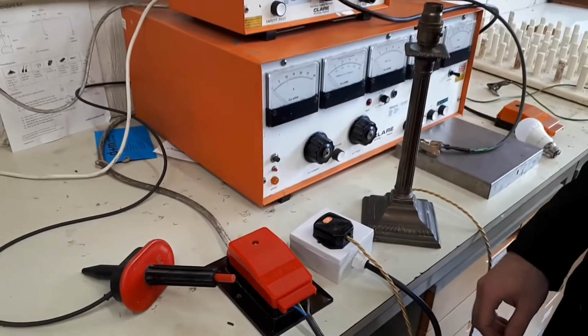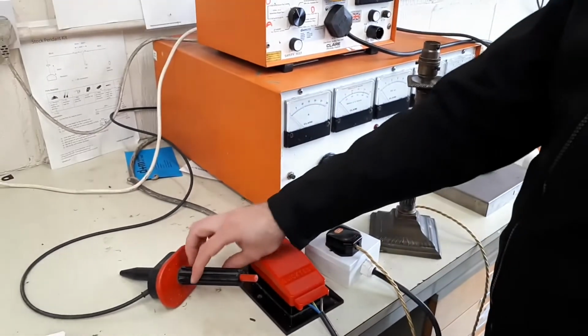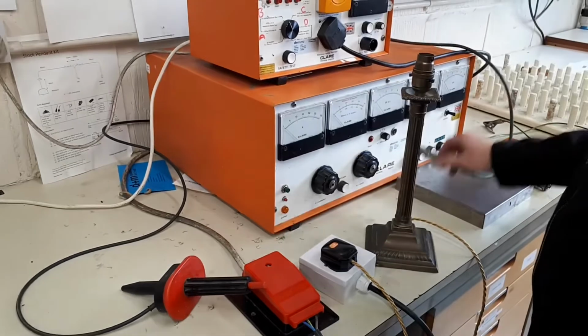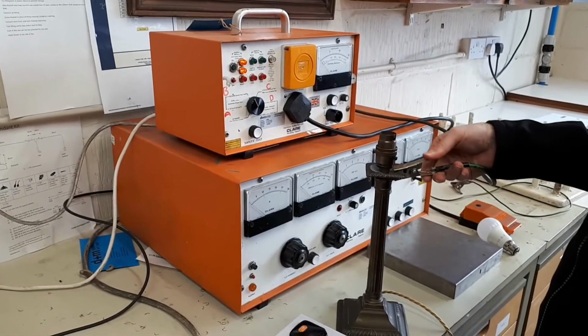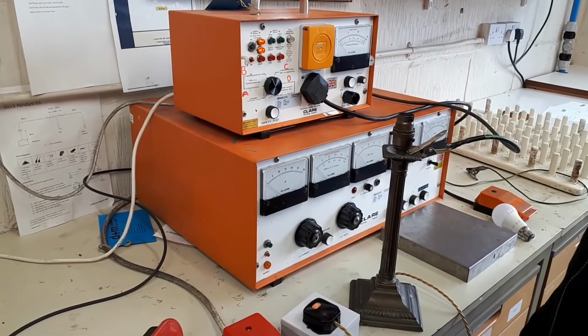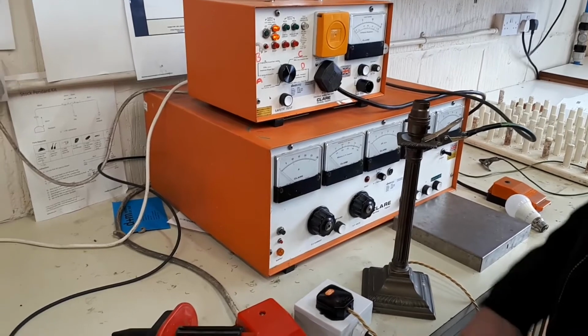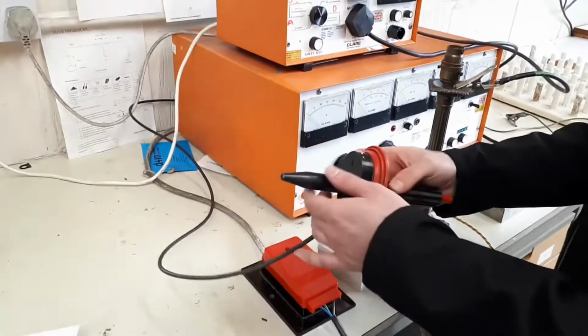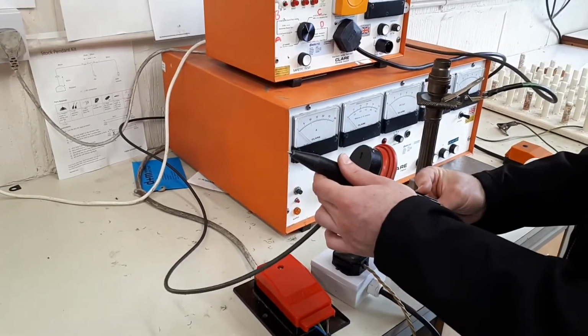For class 1 fittings, we connect the earthing lead to the light fitting using a crocodile clip. For class 2 fittings, we would use the earth probe instead. There's more on this later.